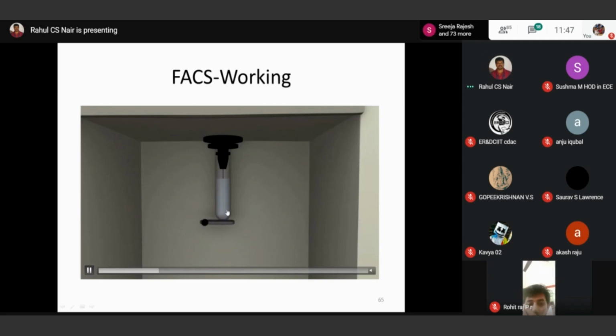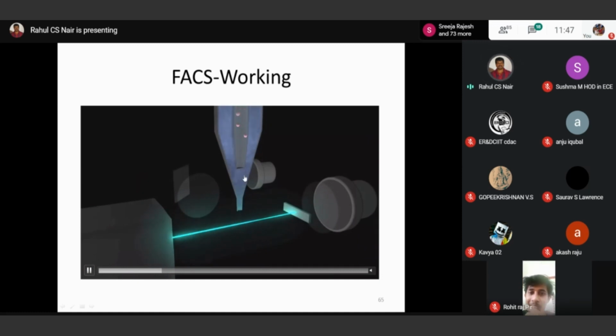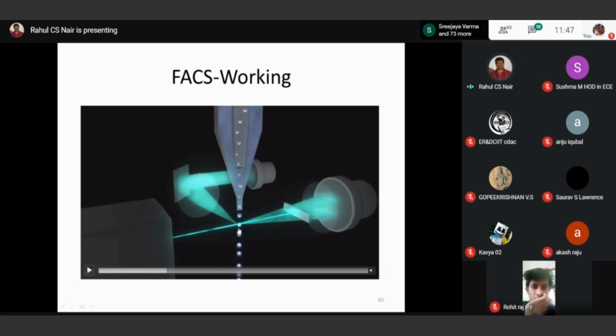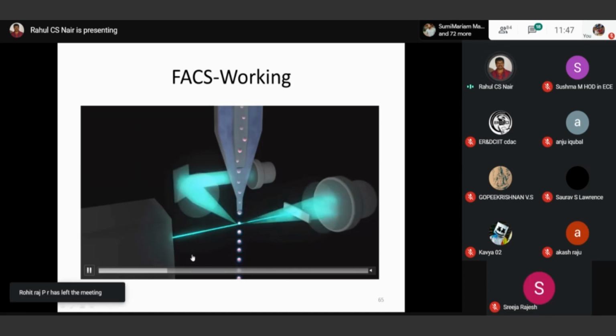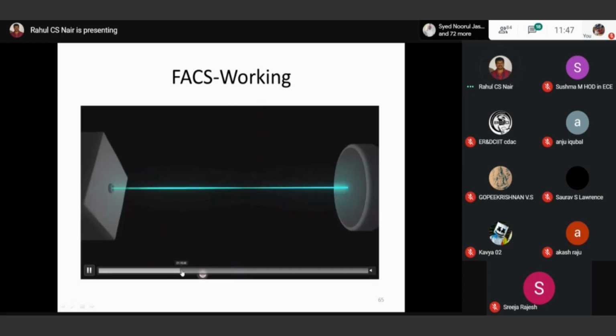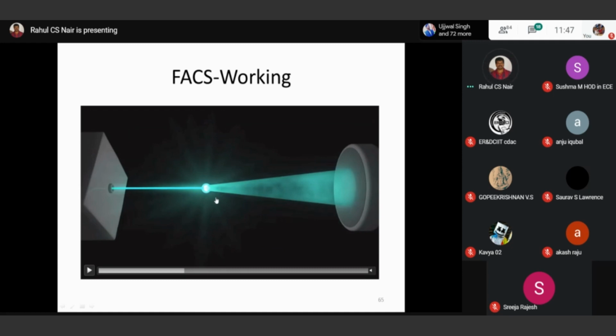Once the sample is loaded, the instrument sucks it up, and it is presented by hydrodynamic focusing before the laser. Once it is placed before the laser, laser light goes forward and sideways also. This is called forward scattering, and this is the side scattering. Forward scattering gives a picture of the size of the cell, as you see here. When a cell comes at the light, from the forward scattered light you can see the size of the cell. It is the size of the cell that matters, and you can use deflection plates with an electric field to sort these cells into specific tubes if you want.